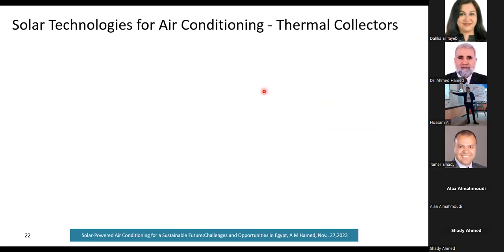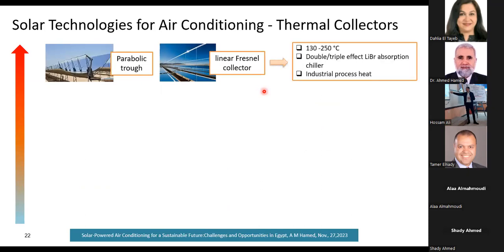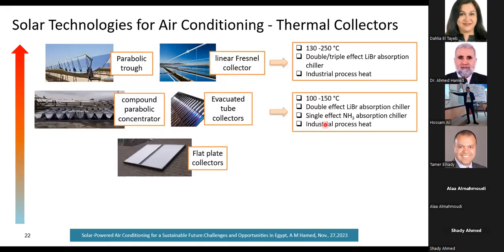Now we go to the solar technologies for air conditioning using thermal collectors. We have different cooling systems which can be powered by heat, but each system has its own specific level of temperature. We will touch on some examples here in the presentation. For example, the double or triple effect lithium bromide absorption chiller is powered by a heat source at temperature levels in the range of 130 to 250. The most suitable solar collector for this case is the parabolic trough or the linear Fresnel collector.